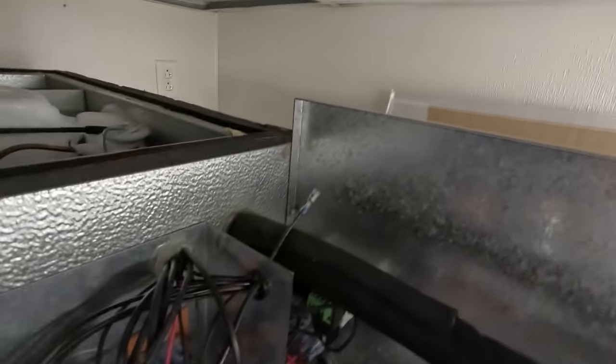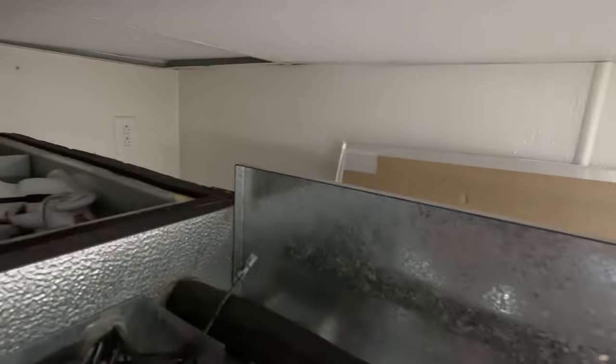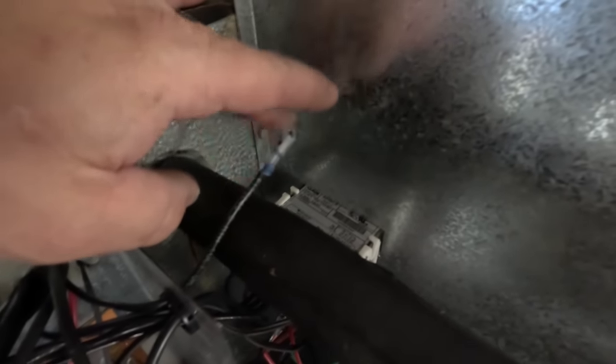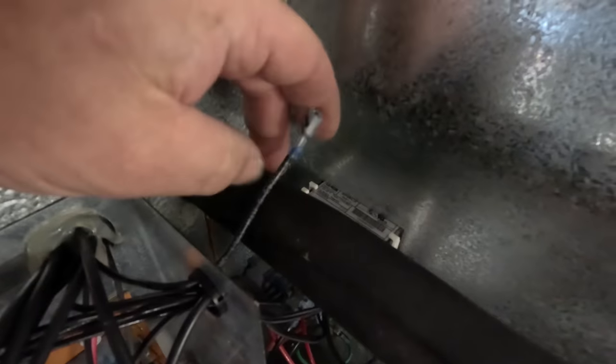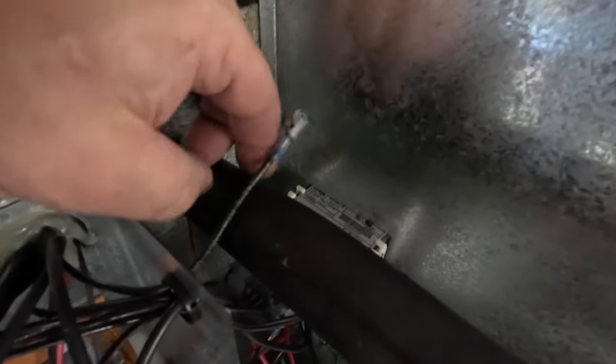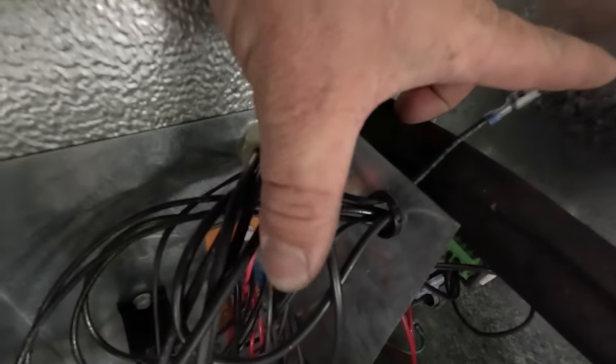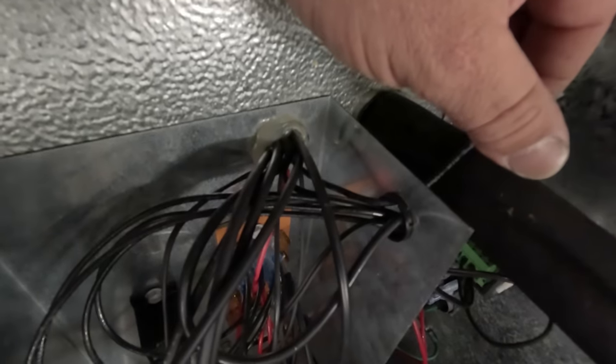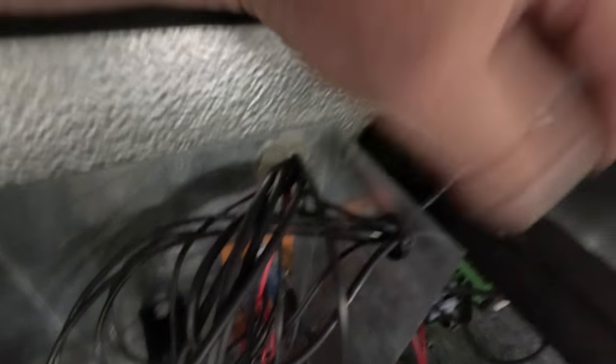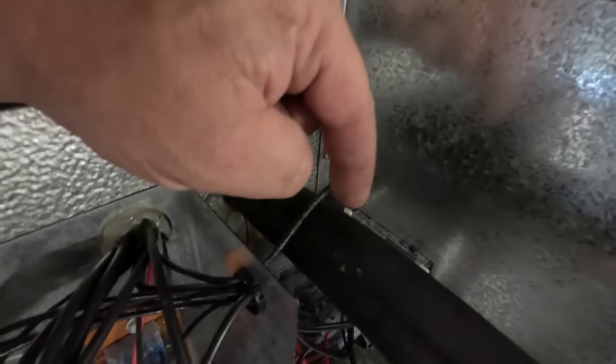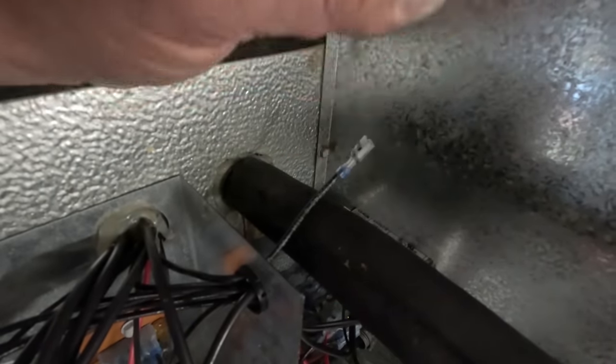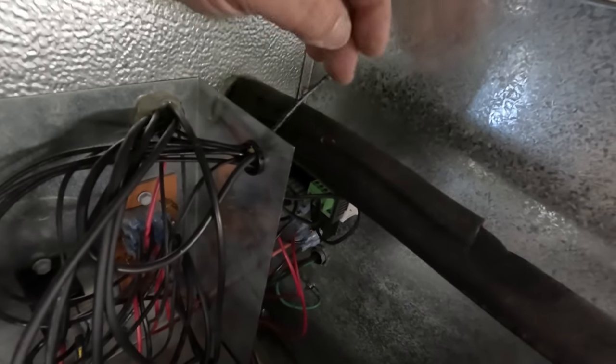Alright. So it's taking some ingenuity here, but what we're going to do, I've unhooked the compressor wire coming out of the controller and hooked the evaporator fans from the motor or from the controller. We're going to run this to a two pole contactor. We're going to power the two pole contactor's coil off of the 230 volt defrost heaters. And so when they're energized, it's going to kill power to the compressor and kill power to the fan. It's generic. It should work now. Well, obviously the thermostat's not working, so I could wire one of those in, but it only has to work for a day or two until we get the other part and then we can reverse it back the way it was. So that's what we're going to do. There's no room up here, so I'm not really going to show you how I did it. Plus it's really not something I recommend unless you really know what you're doing.